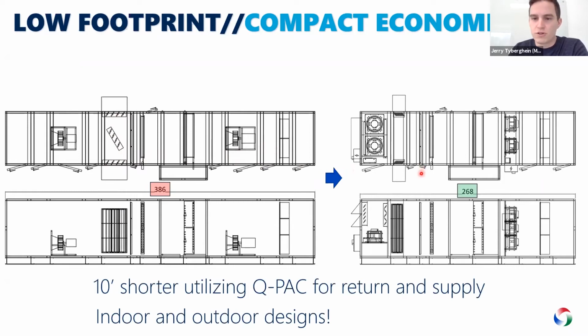Now on the right is our type of unit. So air comes in the bottom, it goes through this vertical ECM fan and it exhausts out the back, or it can recirculate into the supply airstream. We have outside air hoods on both sides now, so that lets us shorten length even more. And then we use QPAC ECM fans for supply as well. So for this example, we didn't tweak the lengths of any other components other than the fans and the arrangement. So all the coils, filters are all the same. So we saved about 10 feet in length just by going to this configuration.